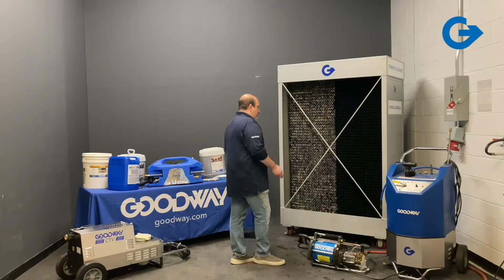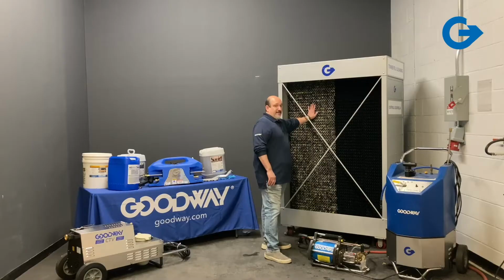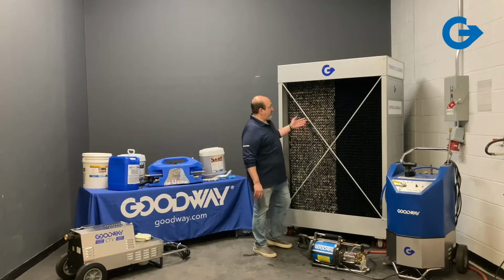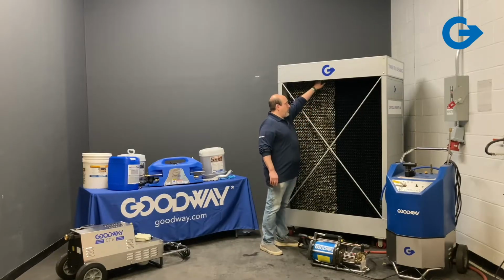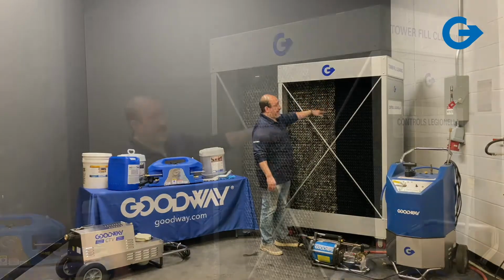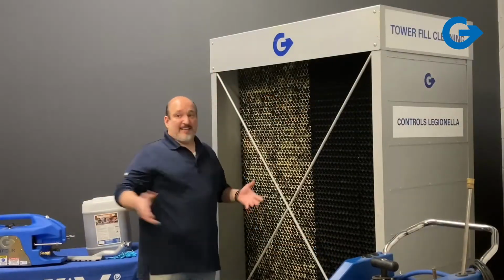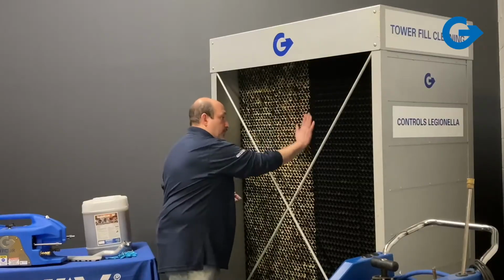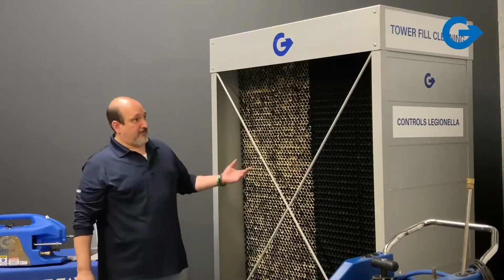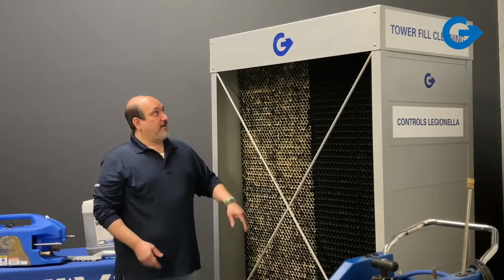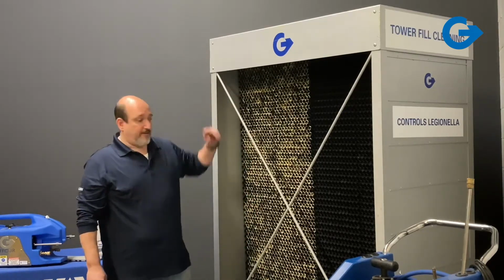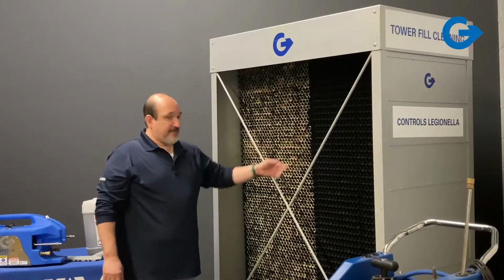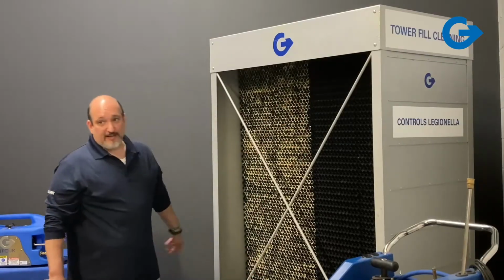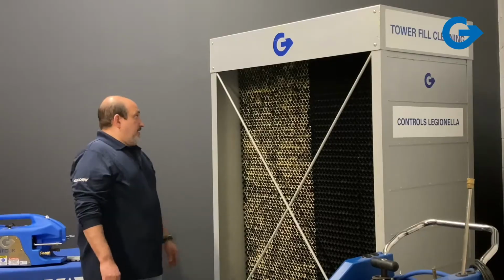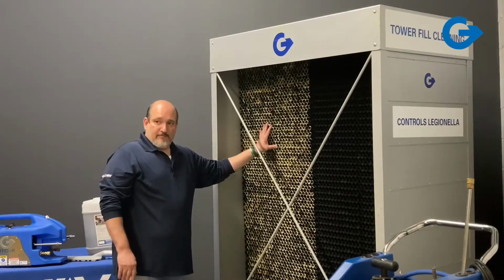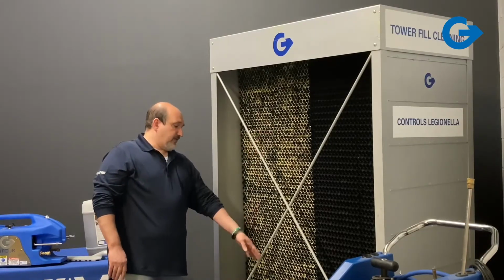The two areas we focused on are the fill and the basin. The fill is this plastic outside coating, and on a cooling tower like this on a cross flow, you have water trickling down the fill. This is where the cooling is taking place, with a fan inside sucking air through this thin coat of water trickling down the fill. The water is coming from your condenser, the heat is getting expelled, and as the water comes back down it's getting cooled, going into the basin, and then back to your chillers again. So the fill is the first part we'd focus on cleaning, and also the basin.